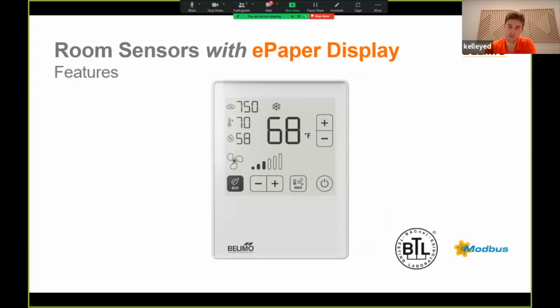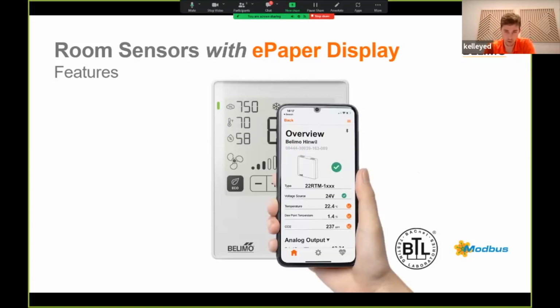All right, so what do we mean by configurable? One thing, you can totally customize the display. In this example, this is a Belimo active room sensor. It's showing the room temperature, the relative humidity and CO2 concentration, with an LED indicator for CO2 levels. It's got temperature set point, ventilation speed, and then a power button to deactivate the display. In addition to that, from your phone through NFC, you can also view live data, set your temperature set point range, change units and analog outputs, and set offsets.